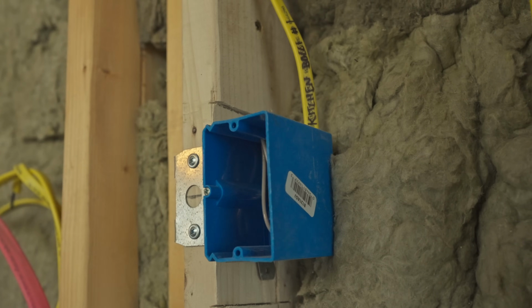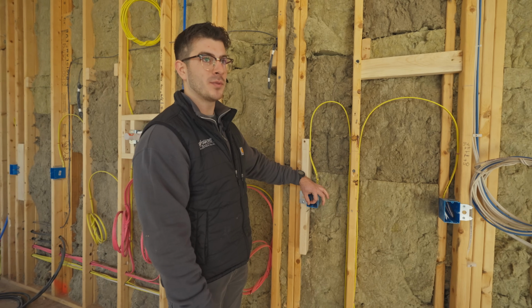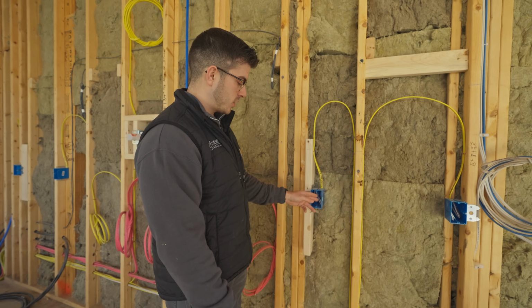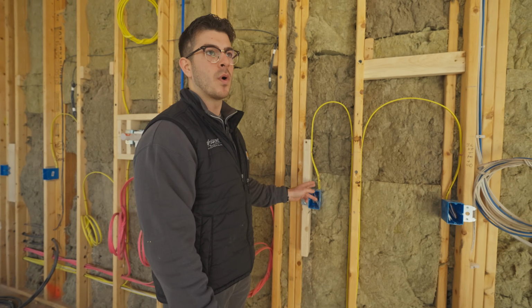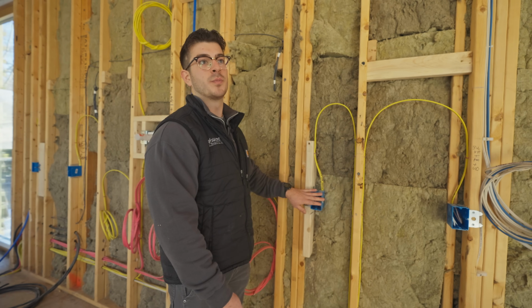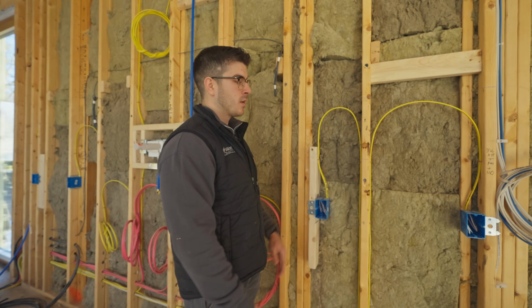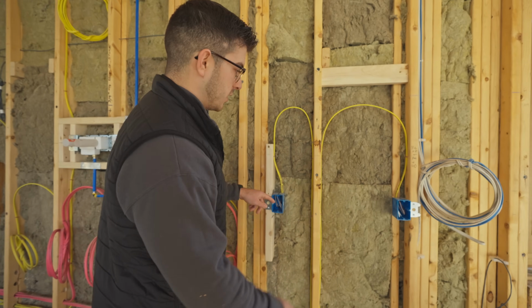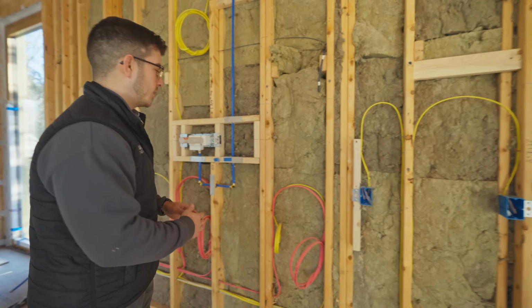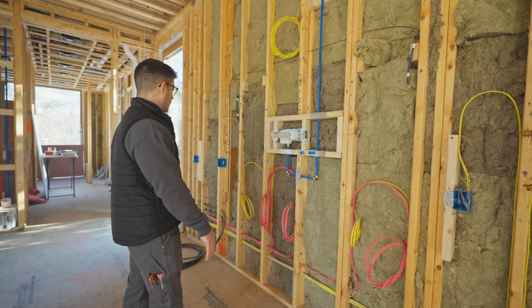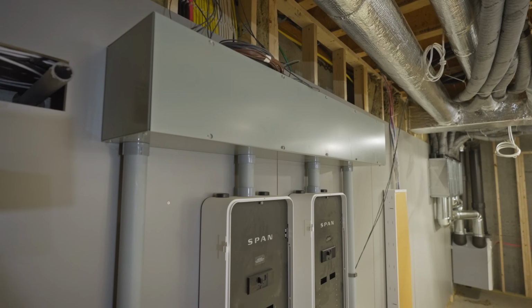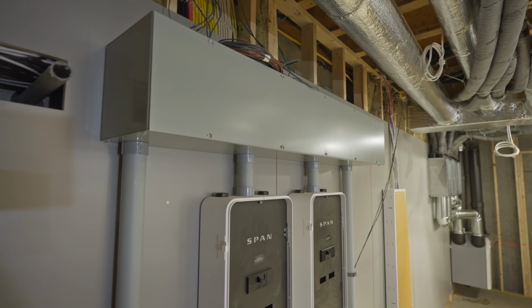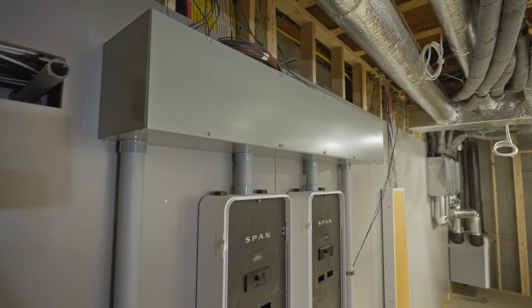That plate actually ends up closing this box space down to about 1.25 inches, in which case the code requires that we only have one wire in each box, so there's no splice in there that you can't get at later. So all of my feeds, there are actually 4 instead of 2, because we have 4 countertop circuits.